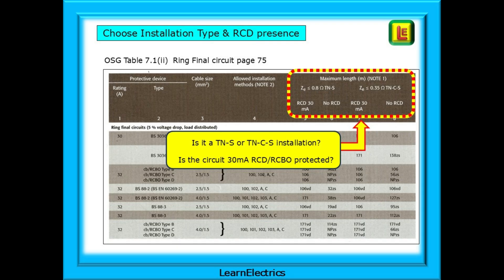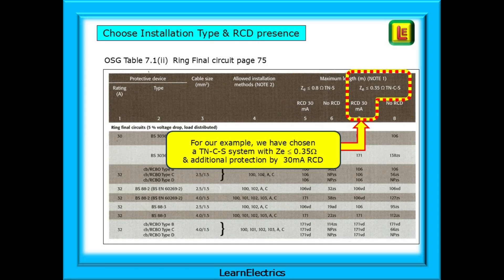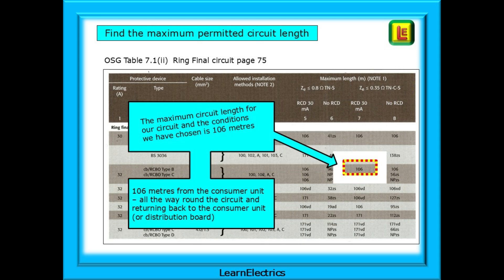Although all new circuits should now have this additional protection as standard. For our example, we've chosen a TNCS system with ZE equal to or less than 0.35 ohms, and with additional protection by 30 milliamp RCD. Now we can find the maximum permitted cable length for the circuit. The maximum circuit length for our circuit and the conditions we've chosen is 106 metres - a ring circuit. That is to say, 106 metres from the consumer unit, all the way around the circuit, and returning back to the consumer unit or distribution board.